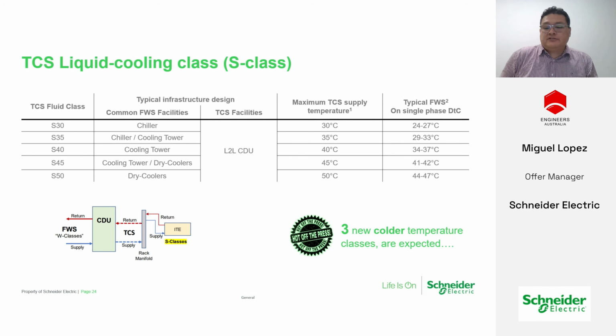The fact is that up until, what are we in, May 2025, there has been an opportunity to deploy very high S50 water temperature thresholds. An S50 water temperature threshold, as you can imagine, gives an opportunity for large amounts of free cooling hours. So if your outdoor heat rejection is a free cooling chiller or whatever it may be, the fact that you're running 50-degree water on the TCS loop means that you really do not need to run compressors to be able to reject that heat. However, 30-degree water loops means that you will be needing some mechanical cooling to be able to achieve a 30-degree TCS water loop. So just bear that one in mind.